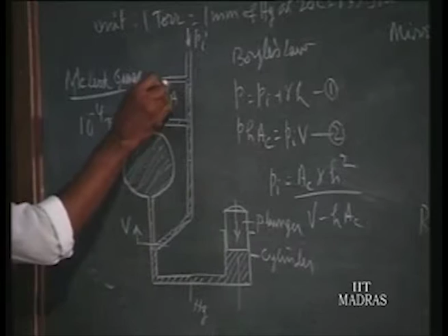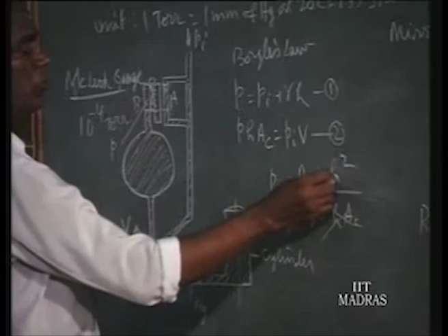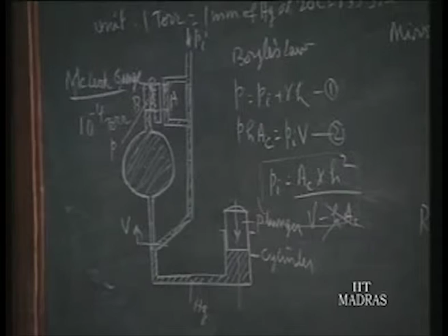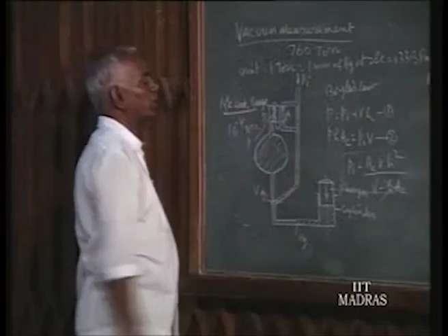Now V is very large when you compare it with the small capillary area, so we can neglect that term. P1 is obtained by measuring the height. All the other terms are constants given by the manufacturer. By measuring the height and substituting in this equation, you get P1. So this is the principle of measurement. This device is used up to 10 to the power of minus 4 torr. For an unknown vacuum pressure, we can connect it and calculate the pressure.